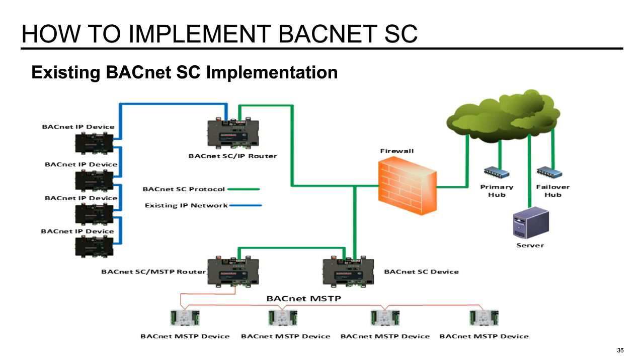Okay, next up we have a question from Cullen. Is there spec language that an owner can add to their automation specifications to ensure that the owner be the certificate authority? I would add very direct language. And if you wanted to, you could even reference the section in the BACnet SC addendum. Yes, the actual section in the addendum is YY.7.4.1.2, and like I said, it requires the signing certificate authority shall be controlled by the site.